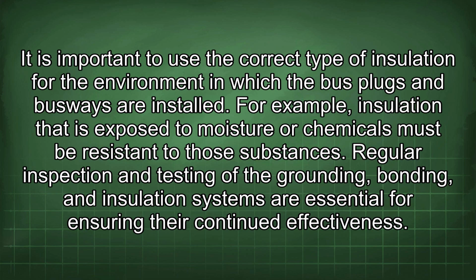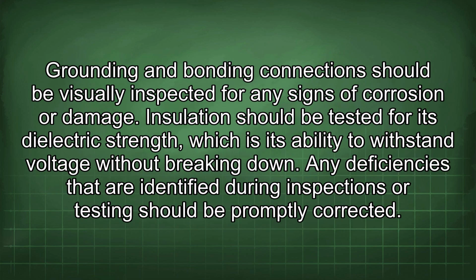Regular inspection and testing of the grounding, bonding, and insulation systems are essential for ensuring their continued effectiveness. Grounding and bonding connections should be visually inspected for any signs of corrosion or damage. Insulation should be tested for its dielectric strength, which is its ability to withstand voltage without breaking down. Any deficiencies that are identified during inspections or testing should be promptly corrected.